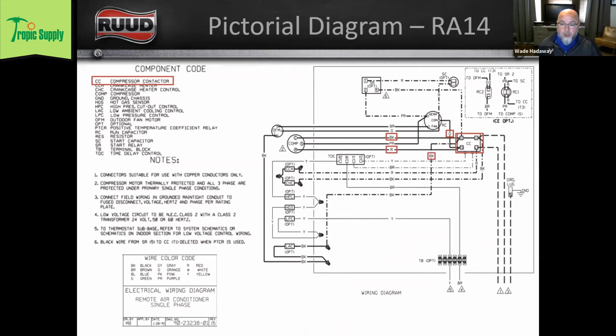The diagrams will also show you optional devices. You can see the dotted wire is for an optional component. If we had the low ambient control, we would wire it from T1 off of our contactor through that low ambient control and then up to our outdoor fan motor. The schematic doesn't show that that part is optional, but the pictorial diagram does. So it's easy to waste a lot of time looking for a component that's not there. So make sure you check both the schematic and the pictorial when you start troubleshooting.